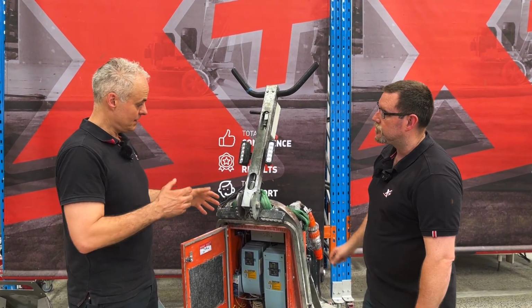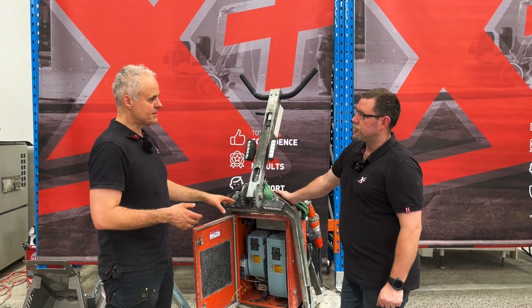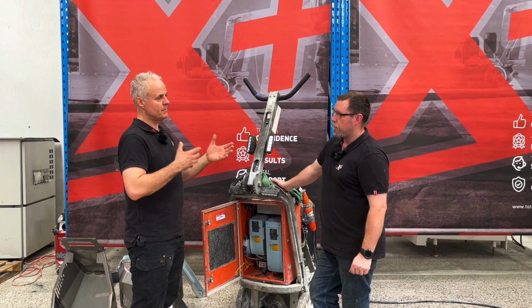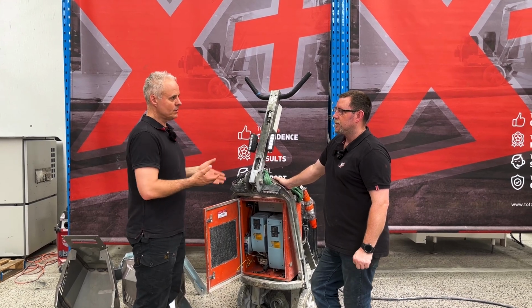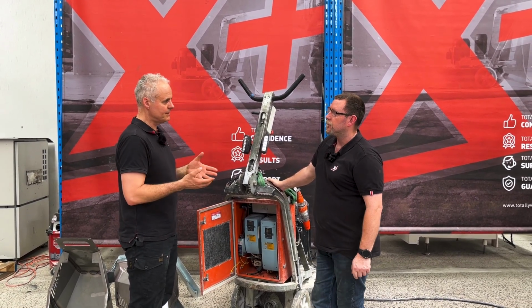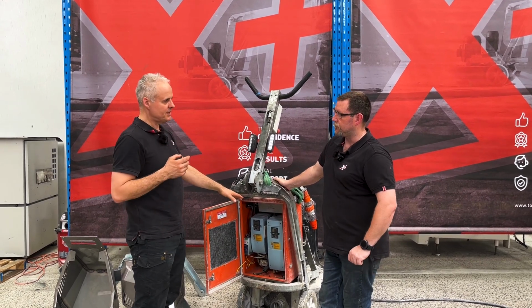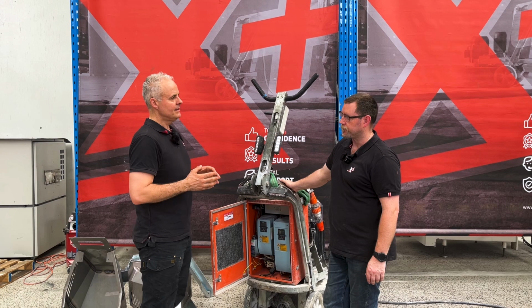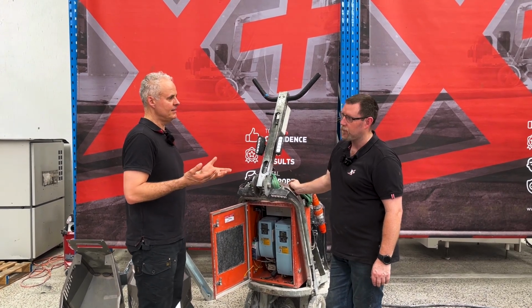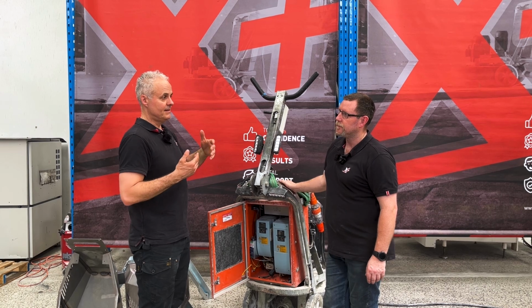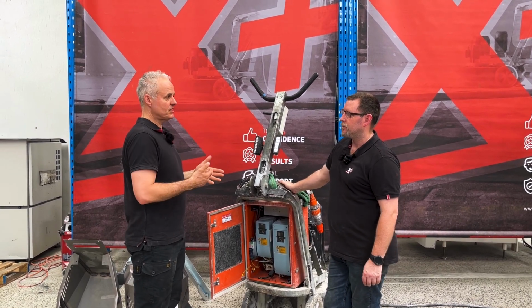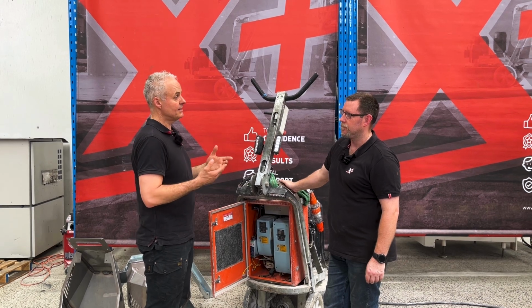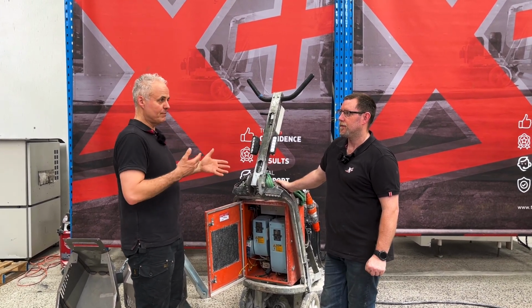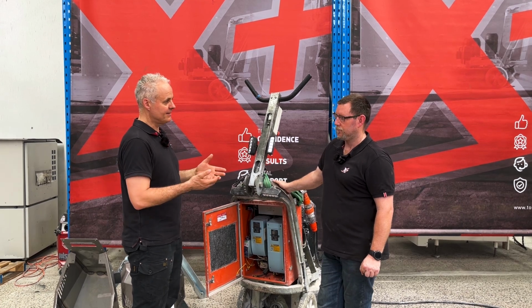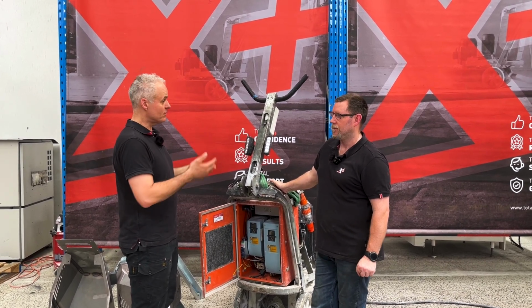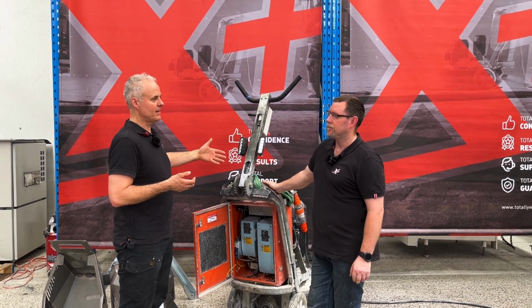Then there's obviously the issue of error codes. These frequency inverters store an error code - every time a machine logs an error, it stores that code. Some store lots of errors, some only store very few. This particular brand of drive, I think, stores only five. Now every time they disconnect the power to the machine, it comes up as an under voltage error. So if they've disconnected or stopped the machine five times in a row, they're only going to have one error code, which is the machine under voltage. So if the machine did have a problem and stored the error for the actual issue, but they've started and stopped it or powered it down and up to try and reset it a handful of times, we've lost the original error code.